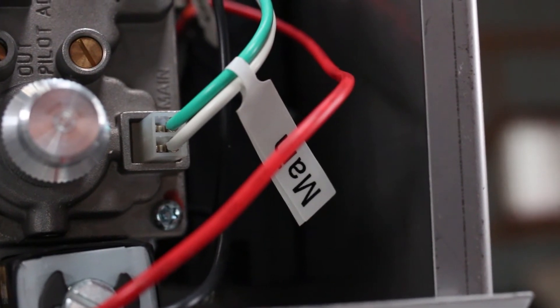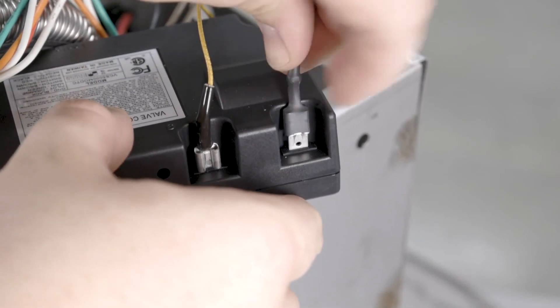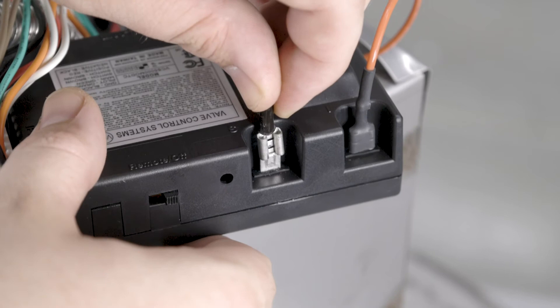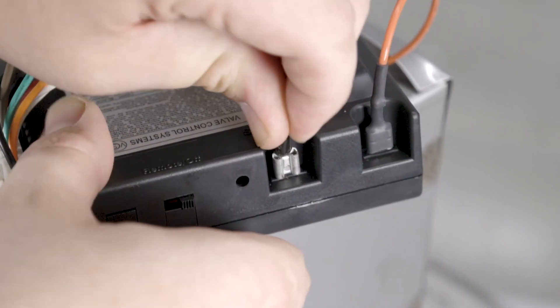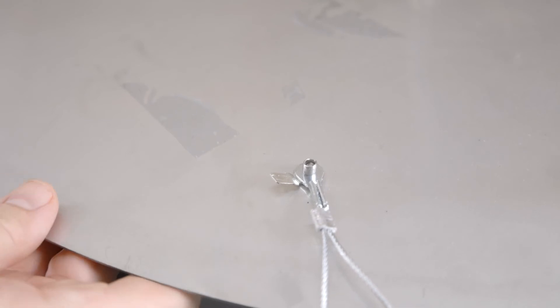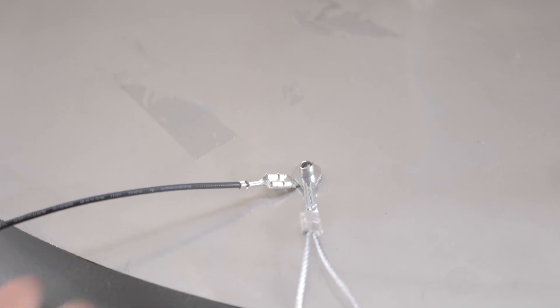Verify the lead from igniter on electrode assembly is connected to the I terminal on the module. Verify the lead from flame sensor on electrode assembly is connected to the S terminal on the module. Verify that the black ground lead from the module is connected to a proper ground on the appliance.